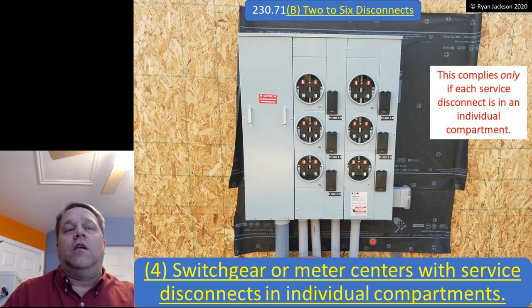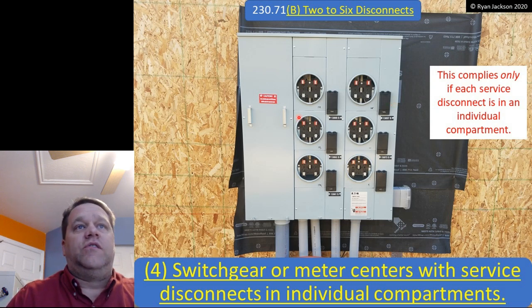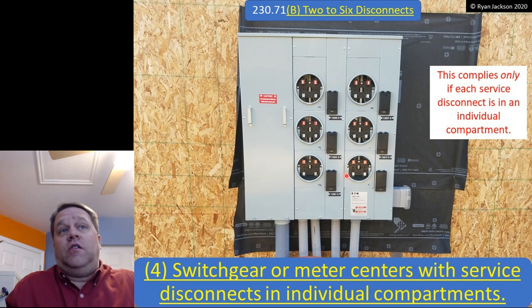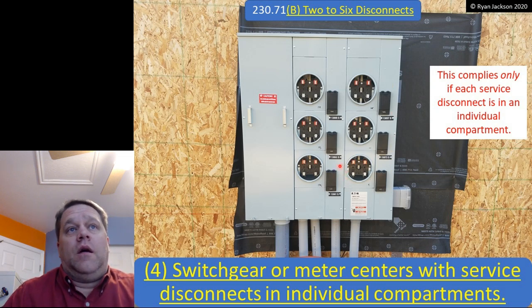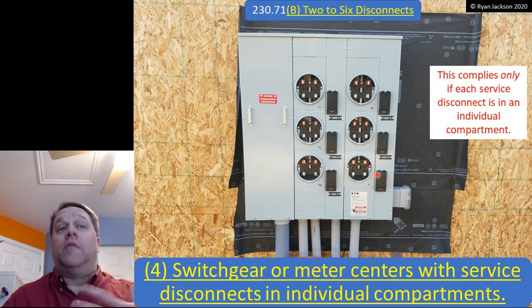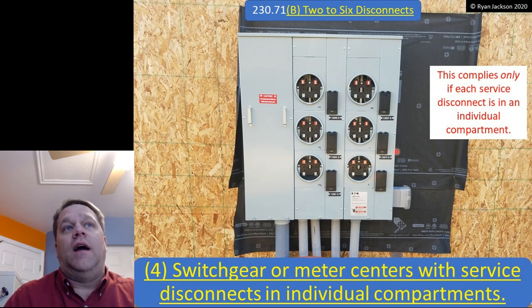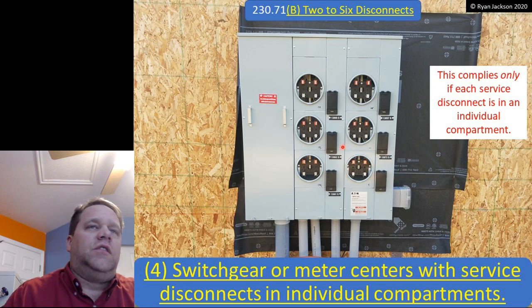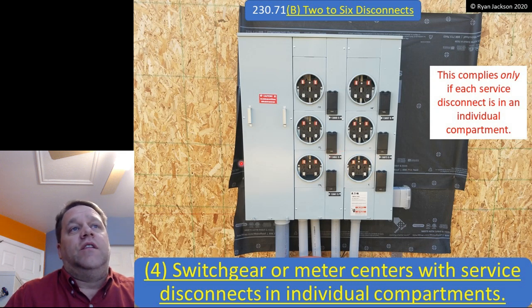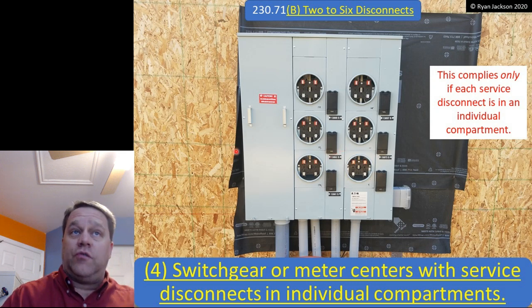This is a set of 5 townhouses plus 1 house meter. So here's my 6 meters, here's my 6 disconnects. You can't use that piece of equipment anymore unless there were individual compartments for each individual service disconnect. And I can tell you from experience, this does not have that. So how would you solve this in the 2020 code? You would have to have a disconnect installed upstream of this panel.